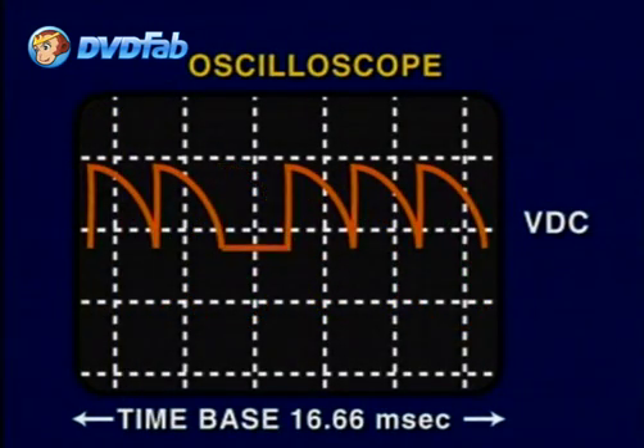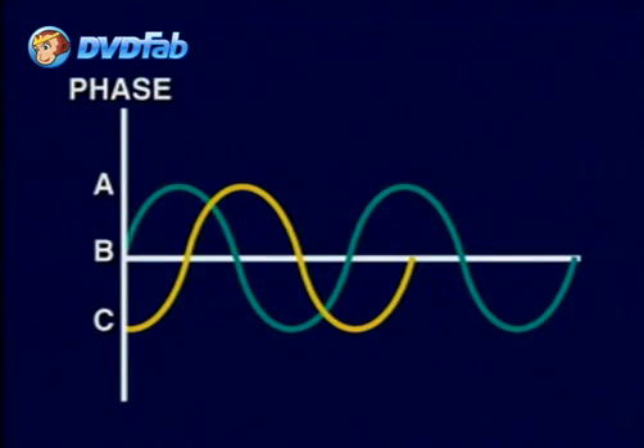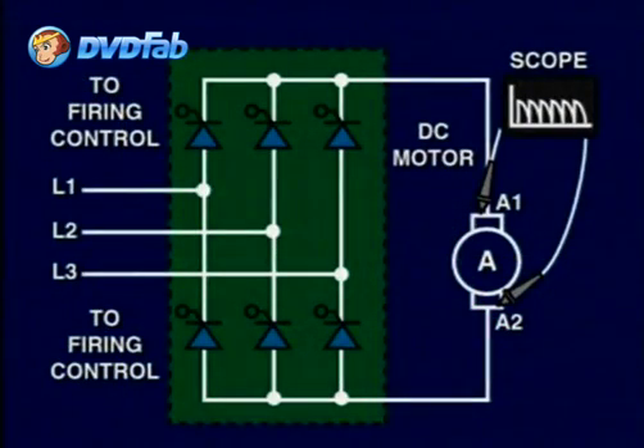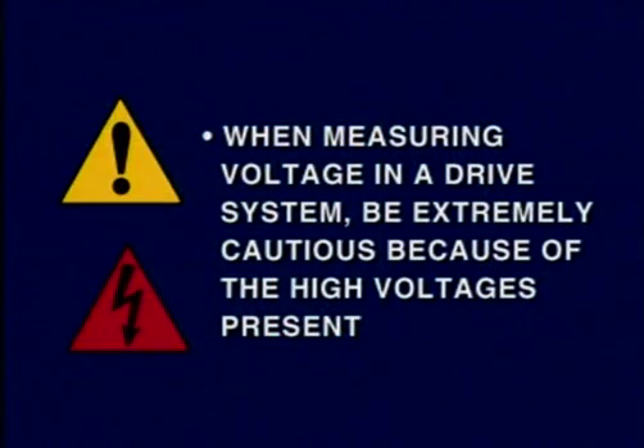If not, one of the SCRs is not firing because of a faulty component. If two of the same phases are not firing, it could be due to a loss of phase. This results in erratic motor movements and slower speed. Additionally, the motor will not have a smooth sound, and it will be reflected in its performance. If you are testing or measuring voltages in the drive system, please be extremely cautious because of the high voltages present in large horsepower motor circuits.